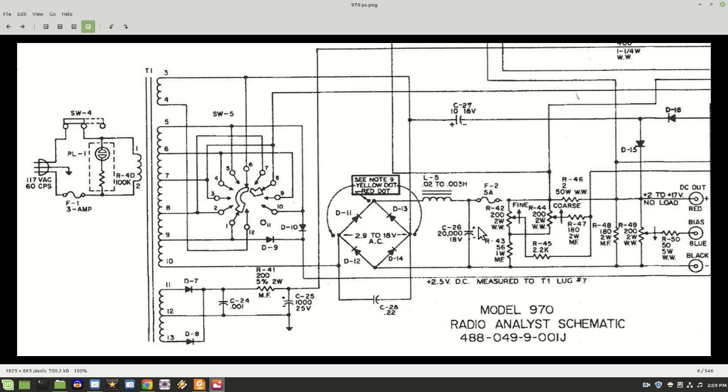That's going to be my whole basis for testing this. If that is the 5-amp fuse that's blown, I'm going to leave it out of the circuit and plug it in. This entire DC output here is isolated. If this fuse here is okay, that means that most of the other stuff is okay and the only problem is right here in this section.